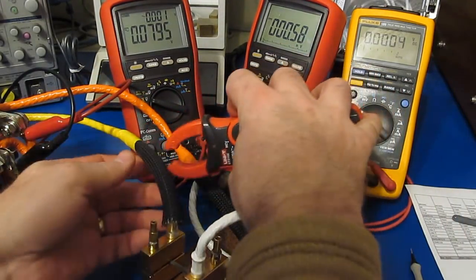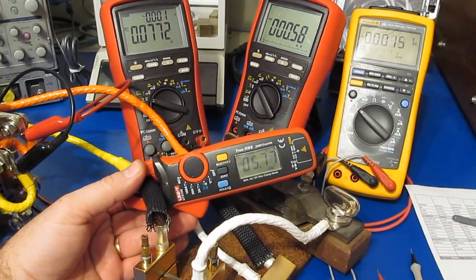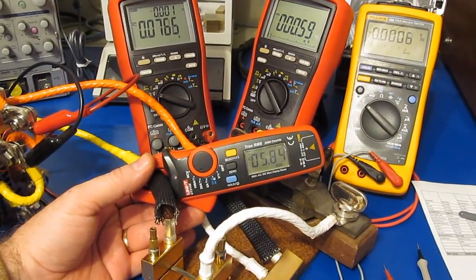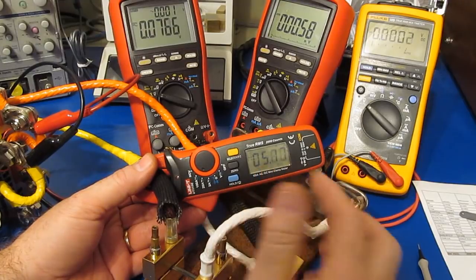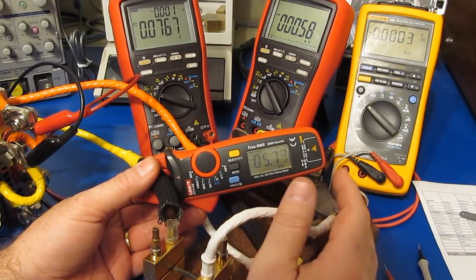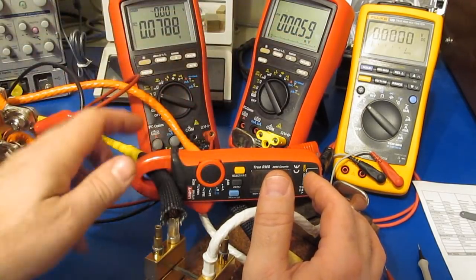I don't have a great spot to place this, but let's see. It looks like it's reading roughly 5.7 to 5.9 amps on the UT210. And on the Brymen BM869s — again, at 50 millivolts it's 500 amps — this is reading 5.8 to 5.9 amps. So these two meters match.